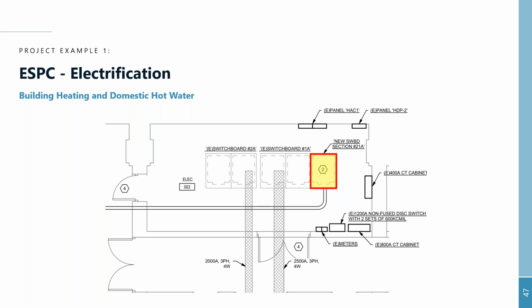For this project, as you see, the gray boxes are the existing ones. There is a little bit of space on the left, a little bit of space on the right, where we could have added some sections to deliver the additional power that we need. This picture really speaks about the demand, the space, and the spare that is required in all GSA projects for the new building. So for new buildings or whatever expansion you are doing, make sure that you meet those requirements, because the next guy that is coming after you to do another renovation on another project needs to use that space.